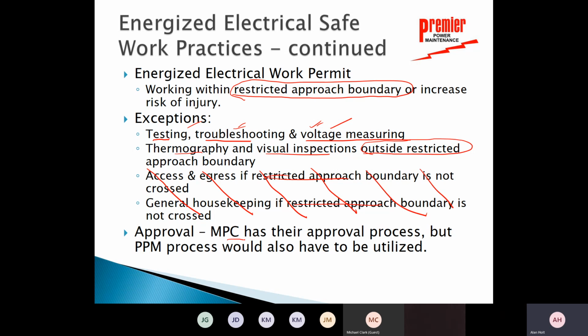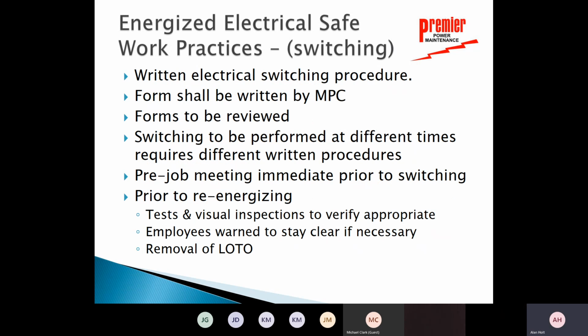Approval. Again, Marathon has their approval process, but again, Premier Power Maintenance, our process would have to be utilized. So, when we talk about actual switching for electrical clearance, Marathon has written out some very specific procedures. They have a written electrical switching procedure for all the switching they do. Now, we don't do that, and we're not required to do that by NFPA 70E. Our procedure is written down only when it's a complex lockout. But Marathon, even if it's not complex, they do have a written procedure.